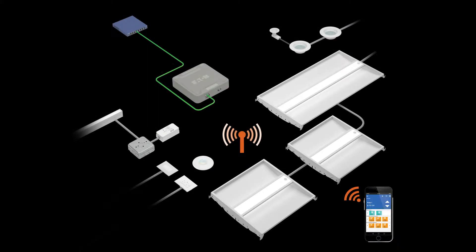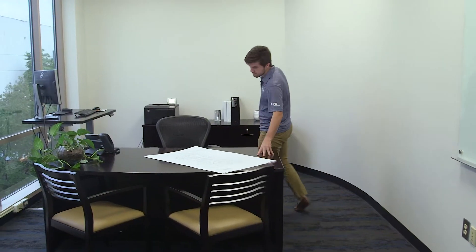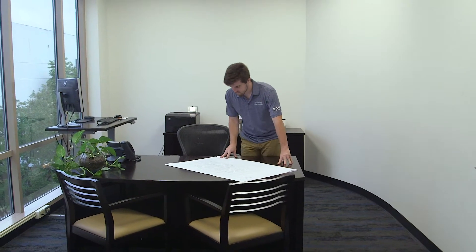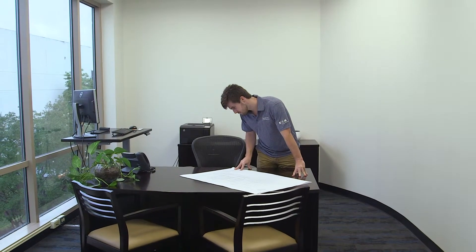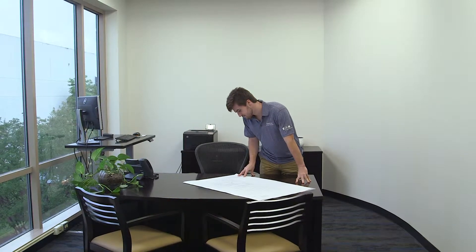Lighting is controlled automatically by occupancy sensors in the space. Fixtures with integrated sensors, wall-mount sensors, and ceiling sensors in the same area are grouped into one control group. If any sensor in the group senses motion, the system will turn on all area lighting to a 50% light level and will turn on all area receptacles.